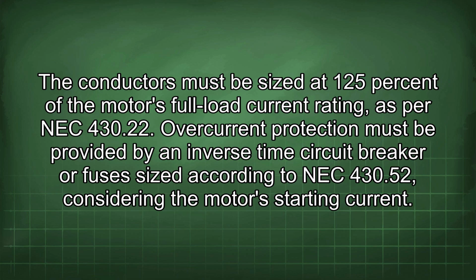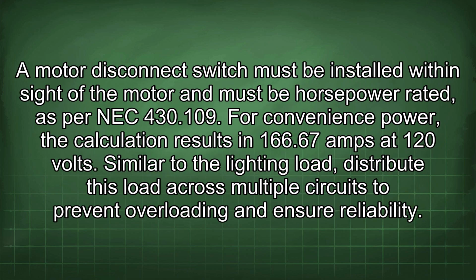430.22. Overcurrent protection must be provided by an inverse time circuit breaker or fuses sized according to NEC 430.52, considering the motor's starting current. A motor disconnect switch must be installed within sight of the motor and must be horsepower rated, as per NEC 430.109.